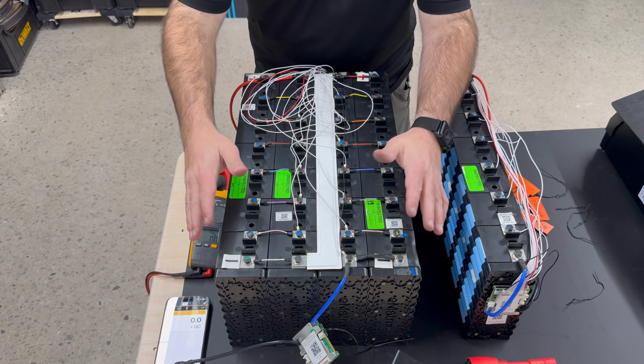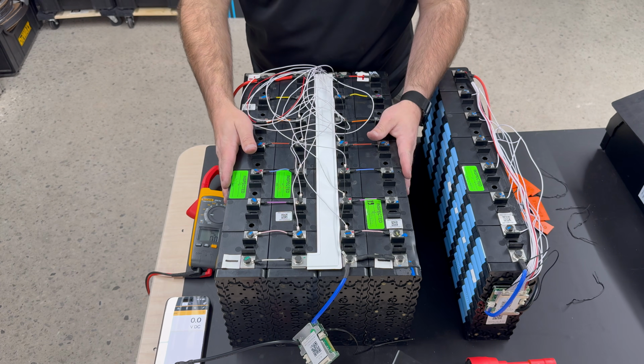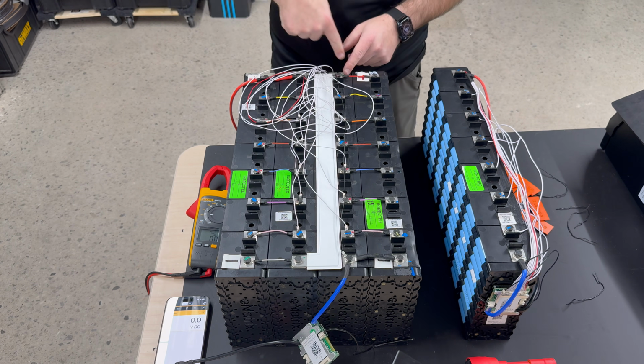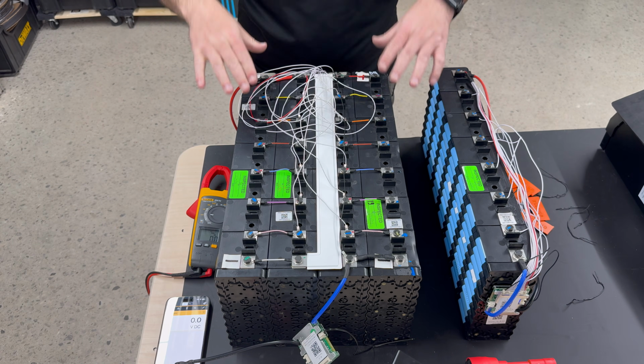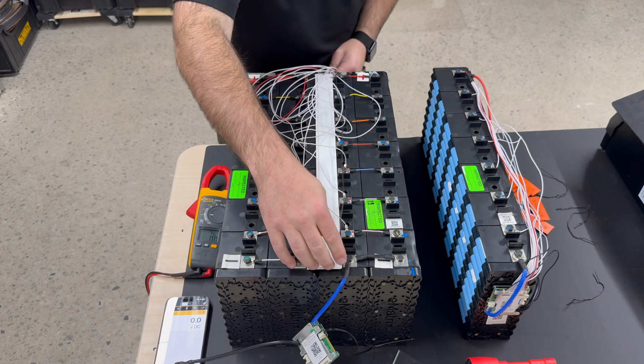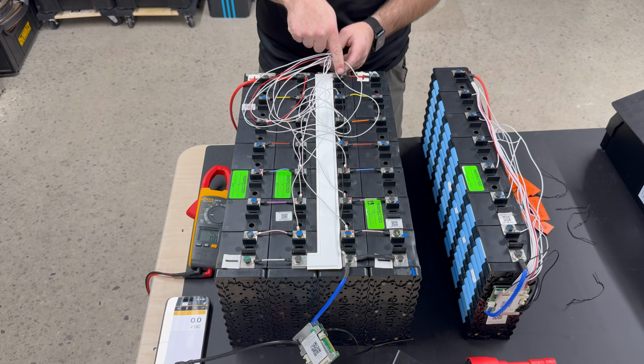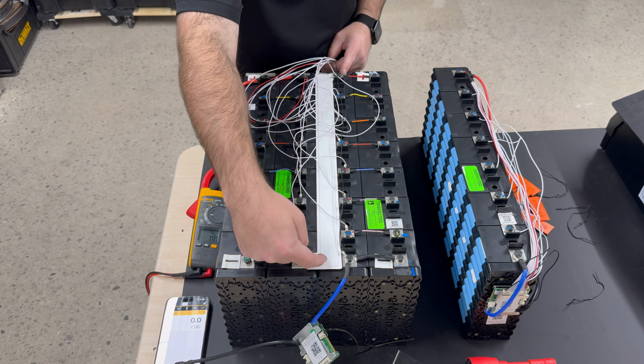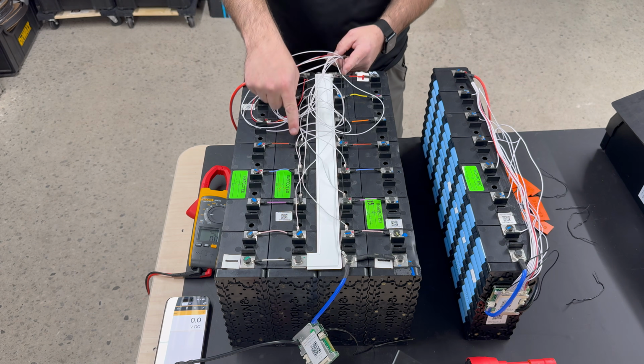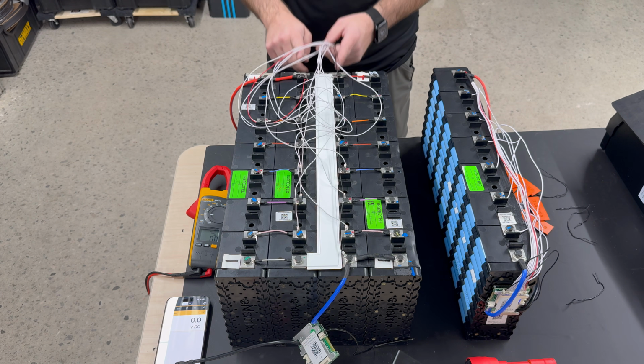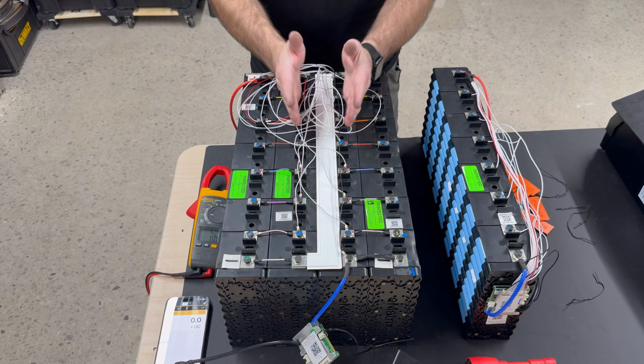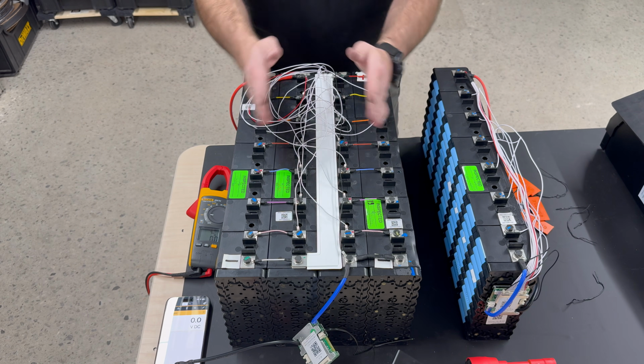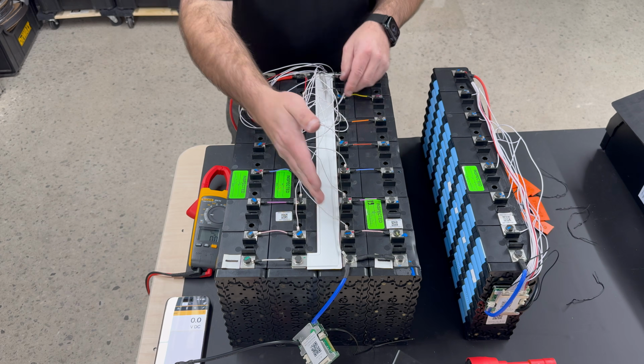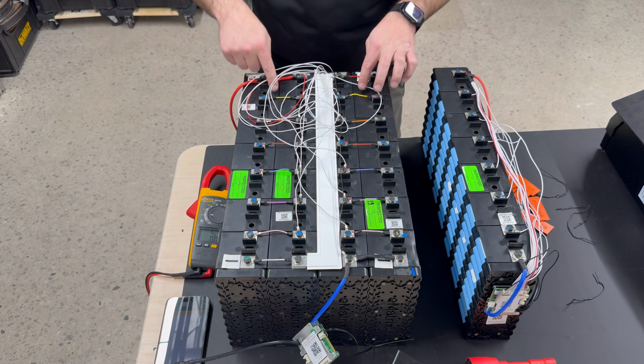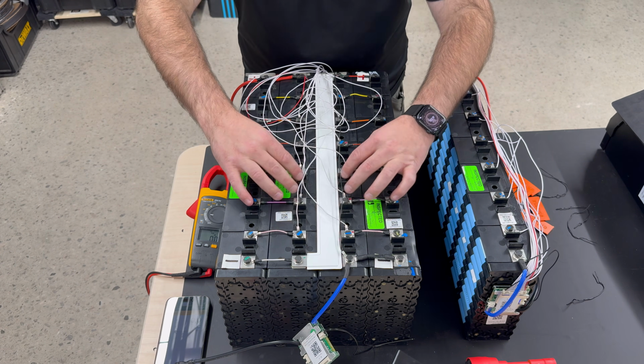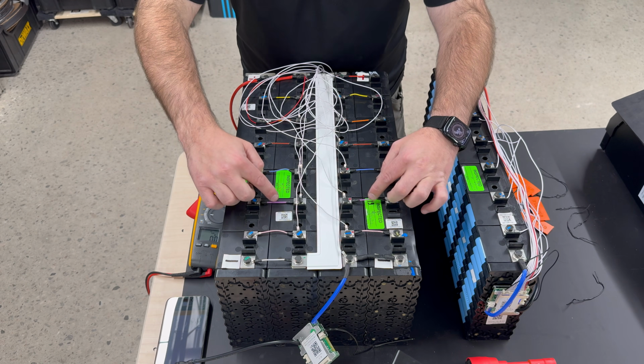So now that I've got these 4 eMatrix modules hooked up, 2 in series and then 2 in parallel, it's now 7S on this side, then connected into series with a bus bar, and then all the way up to 14S, making it a 48 volt battery. And then these two modules on the outside are just paralleled with the inside ones. So the sense wires no longer have to cross over silicone wires that are on the balance leads, and they're not crossing over each other.